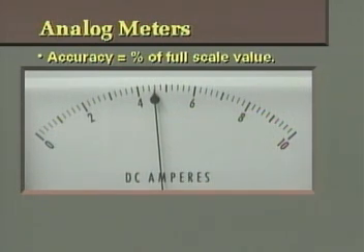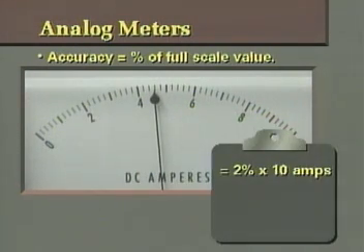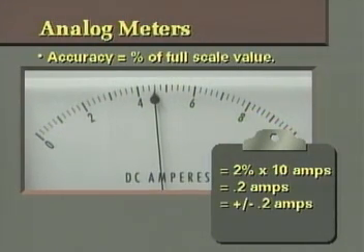Since we said the accuracy for d'Arsonval movements is usually 2 percent, that means 2 percent of the full-scale reading, which for this meter is 10 amps. 2 percent of 10 equals 0.2, which means the accuracy of any reading on this scale would be plus or minus 0.2 amps.